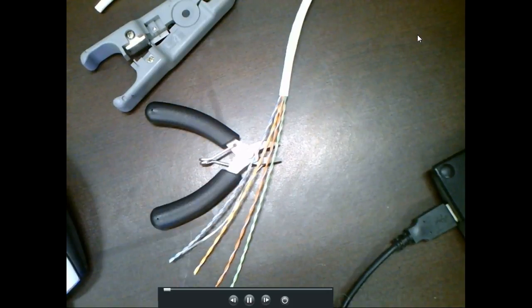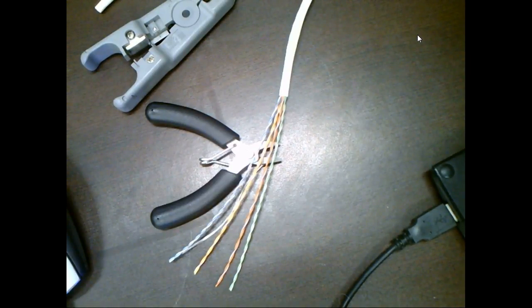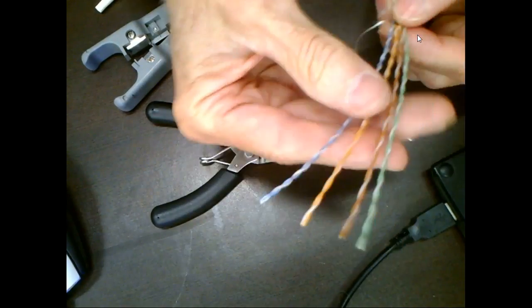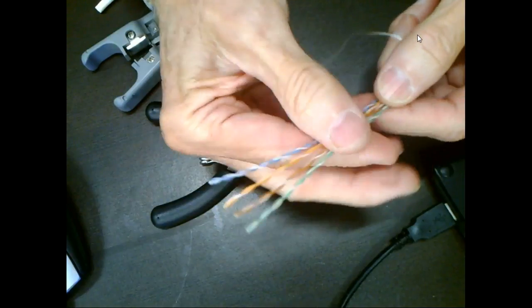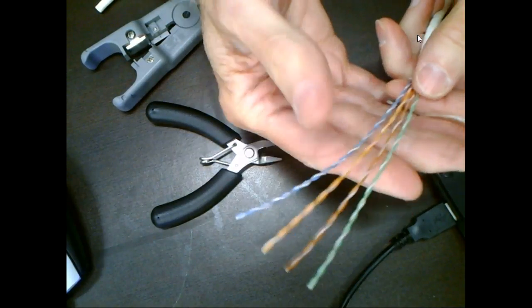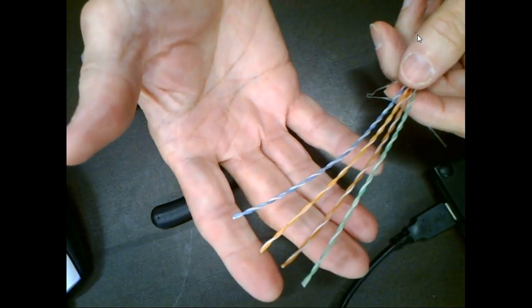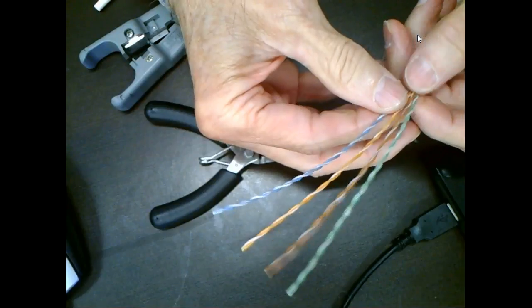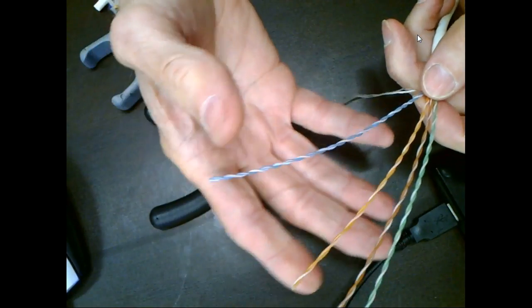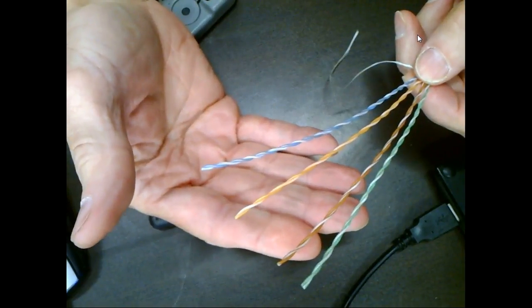Rule of thumb, when you run a cable, you want to use more than you actually need. What we do is strip off about 4 inches so we can unwrap the cable, because if you get down in here, it's almost impossible to get them unwrapped, straight, and arranged correctly. Then we can untwist them, arrange them according to their correct order, and clip them off the right length to put the connector on.